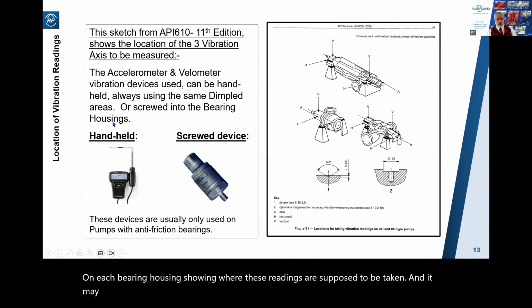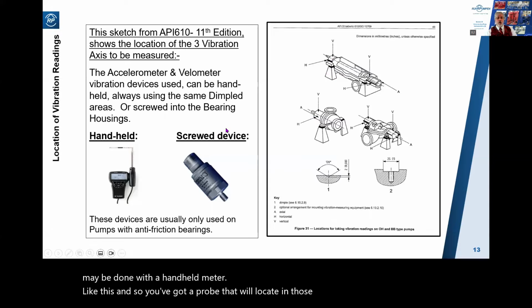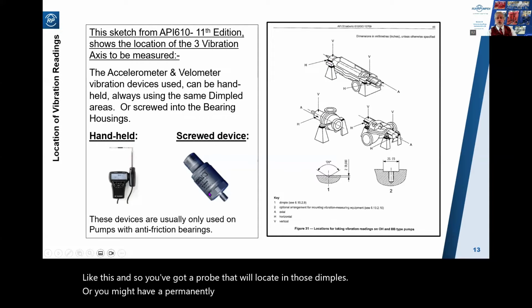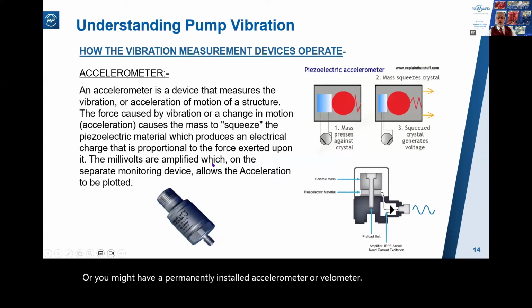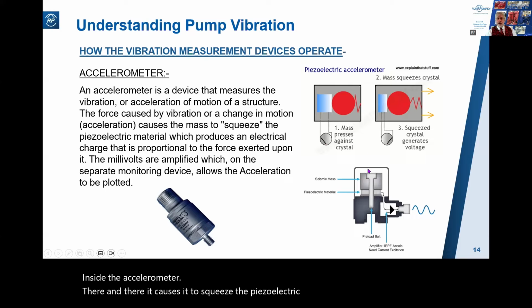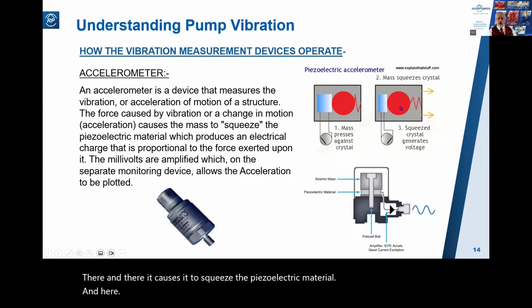And it may be done with a handheld meter like this. And so you've got a probe that will locate in those dimples. Or you might have a permanently installed accelerometer or velometer. This slide shows simplistically how an accelerometer works. Vibrations from the pump housing, the bearing housing, cause the mass inside the accelerometer, there and there, to squeeze the piezoelectric material here and here. And this produces an electrical charge proportional to the force exerted, proportional to the vibration.